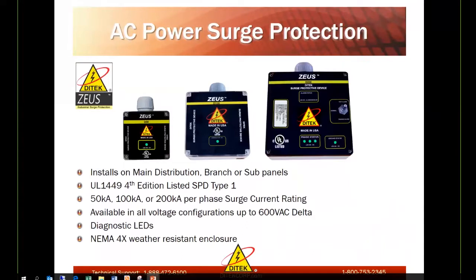Our AC power surge protection line, that right there is our Zeus line. We offer it in 3 surge current applications, 50, 100, and 200. Typically we size higher according to the amp load of your service. It's a UL 1449 4th edition unit. All of them are a Type 1 line side device. So we do offer them in all voltage configurations, whether it's single phase, 3-phase wye, 3-phase delta, and also we offer a high-leg device in each one of them.